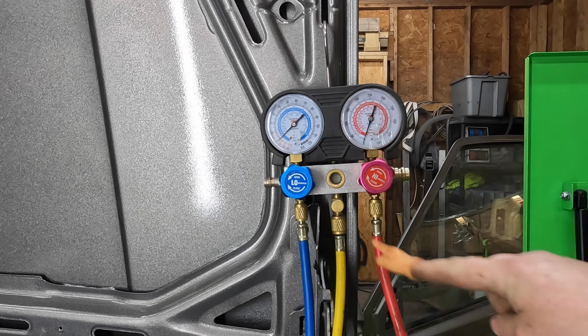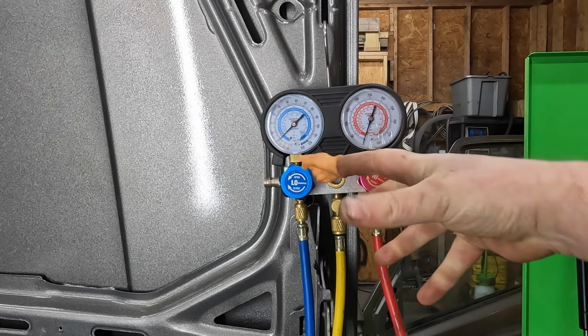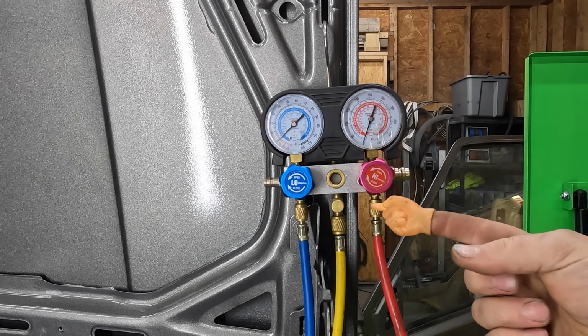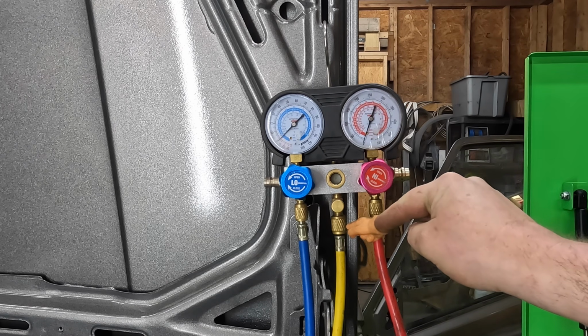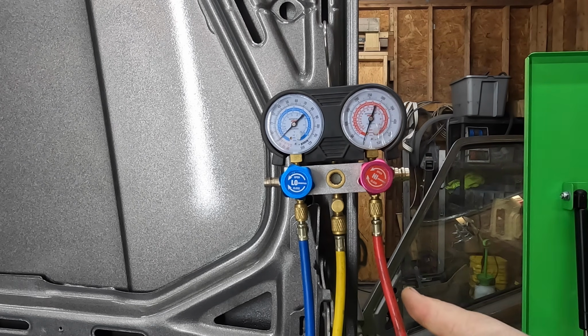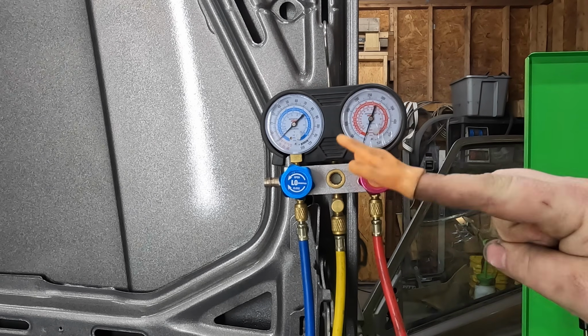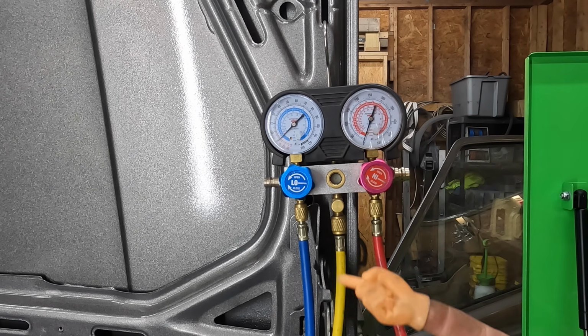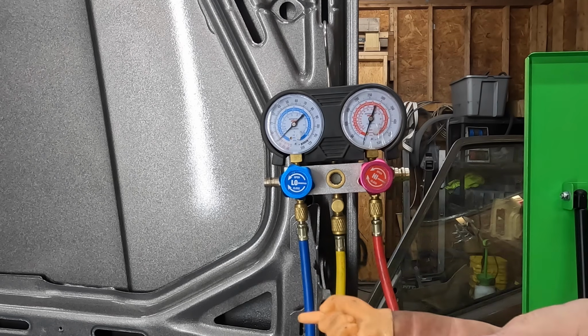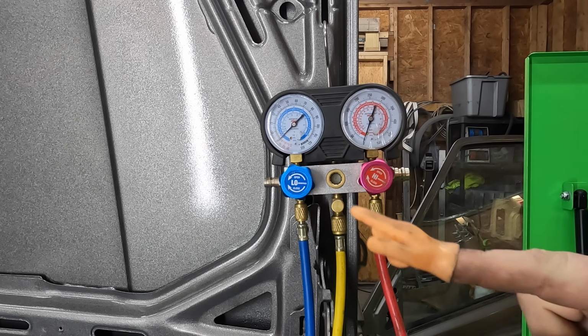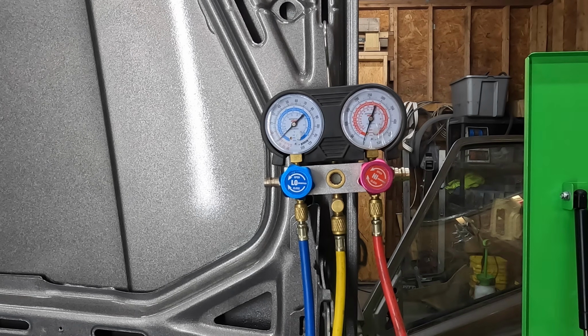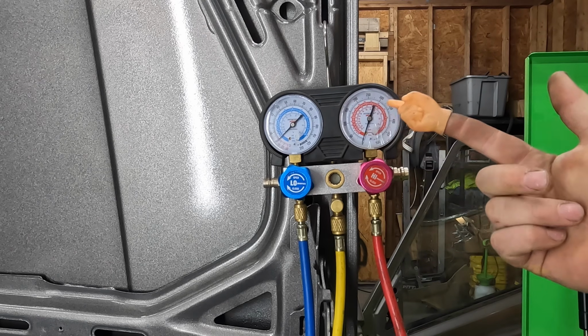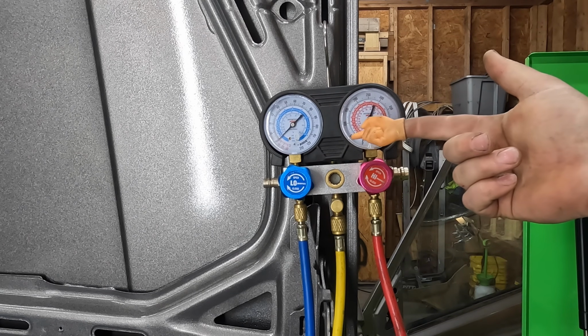So now that everything's hooked up, I can start pulling a vacuum on the system, but first I'll explain some more things. The reason it is important to vacuum down the system before you go charging it is because R134a and other refrigerants, when they are introduced to water or moisture in the air or in the system, do some chemical-y wizardry and you end up with hydrofluoric acid, which will eat pretty much everything, most notably your aluminum and your seals. So you want to keep that out of there. And of course, having just put the system together, we're going to have ambient moisture still left in there. So vacuuming it out will drop the pressure enough so that all that water will boil out of there. Furthermore, that allows you to leak check it quite easily when you have vacuum on it.